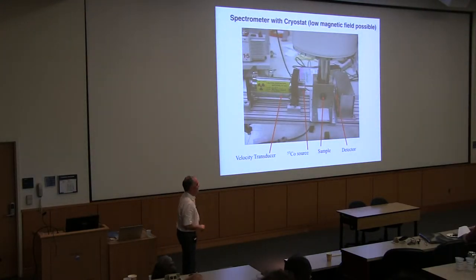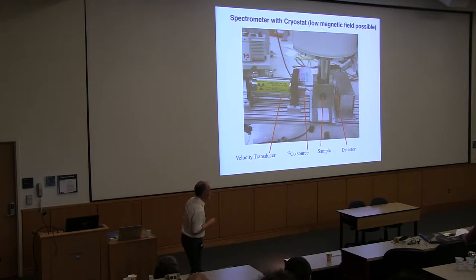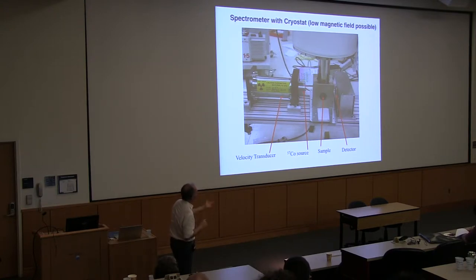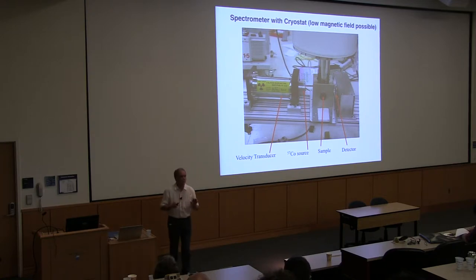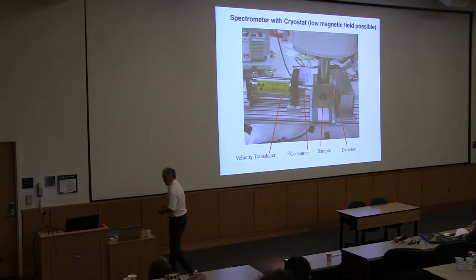The sample in a practical experiment — particularly in bio-inorganic chemistry or biochemistry — we have to freeze, because it has to be a solid. We cannot measure on a fluid solution, but we have to freeze the sample or have a powder. We have the Mössbauer drive unit, the detection system, and we need electronics to drive this velocity profile for the recording, plus gamma electronics and recording electronics. This practical setup uses a cryostat — the pot with a tail section is a cryostat for liquid helium or liquid nitrogen. There is a Mössbauer motor, a velocity transducer, and a detector. The whole thing is properly shielded so that nobody is exposed to ionizing radiation when the system is operating.